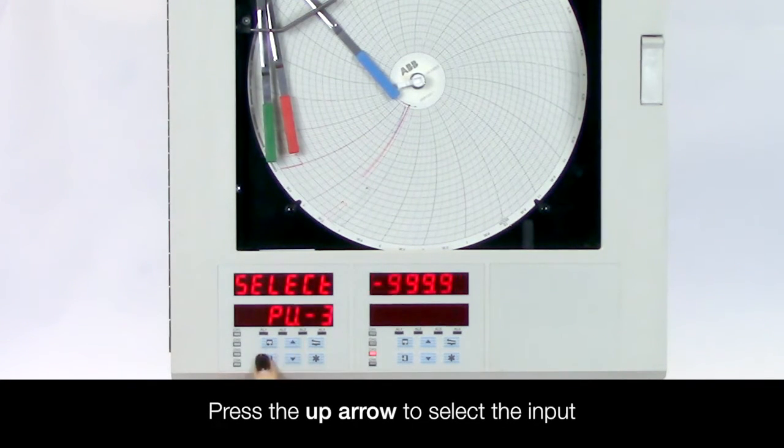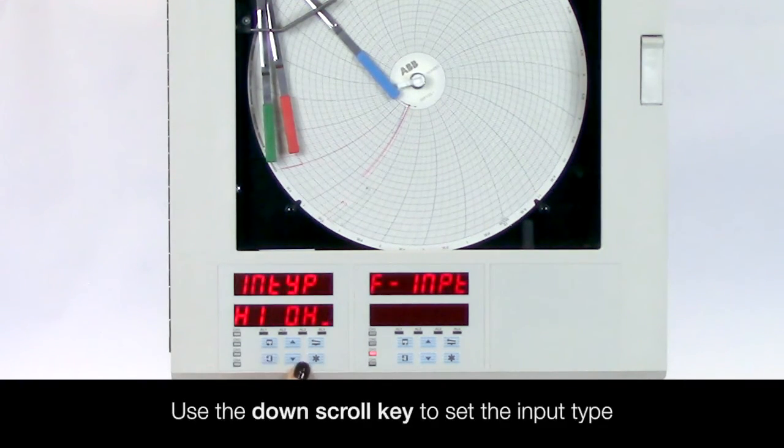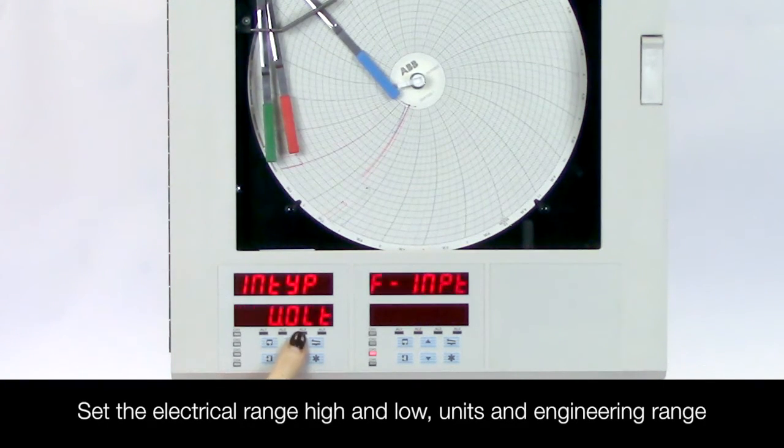Next press the up arrow to select the input you wish to configure and then the down scroll key to set up the input type. You would then set up the electrical range high and low units and engineering range.